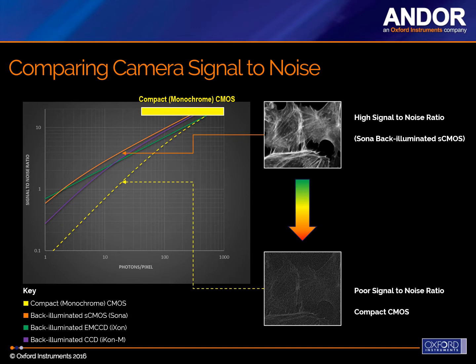Back-illuminated sCMOS cameras give a high SNR under slightly more demanding conditions. And ultimately, due to the EM gain technology, EMCCD cameras still deliver the best image at very low light levels, operating effectively with very small numbers of photons per pixel.